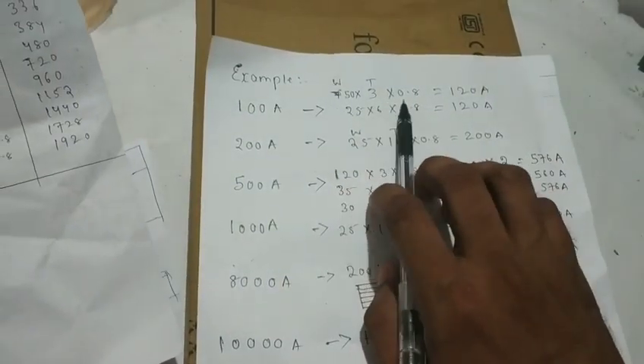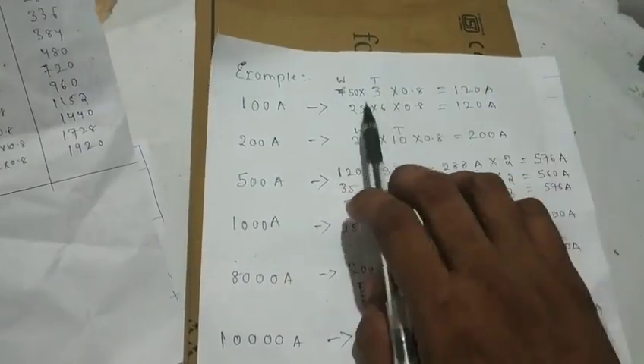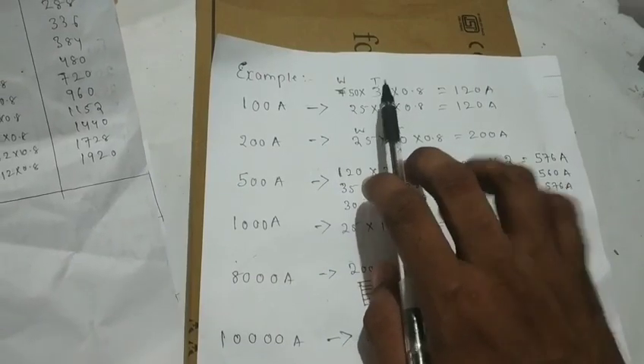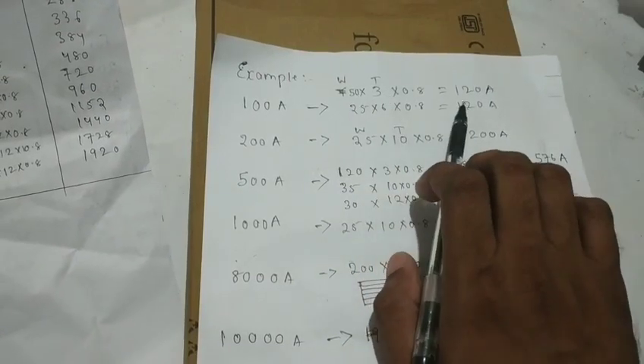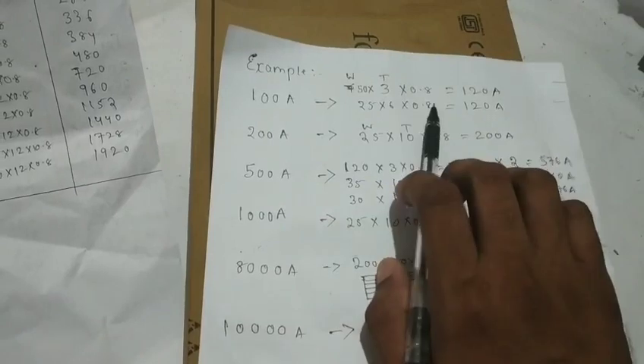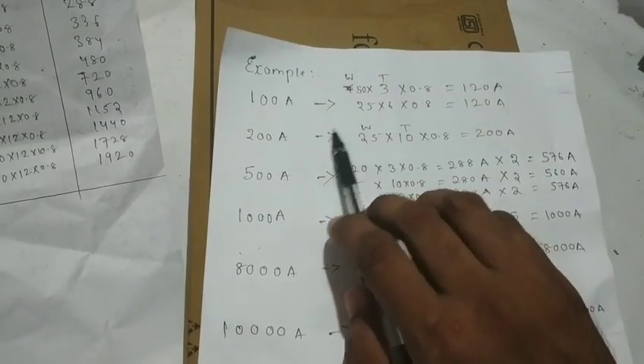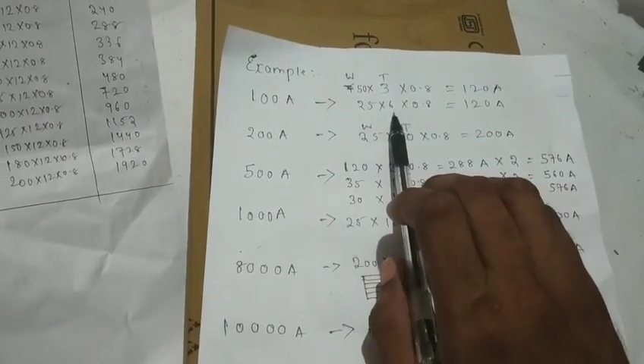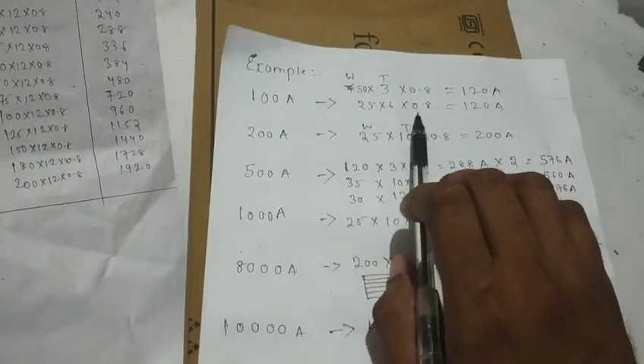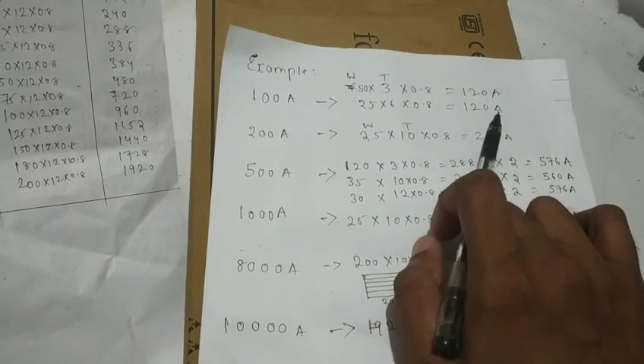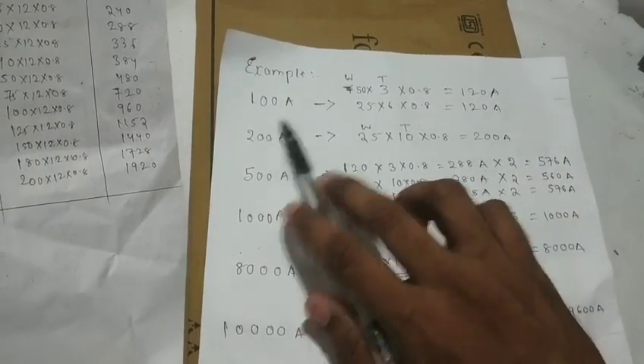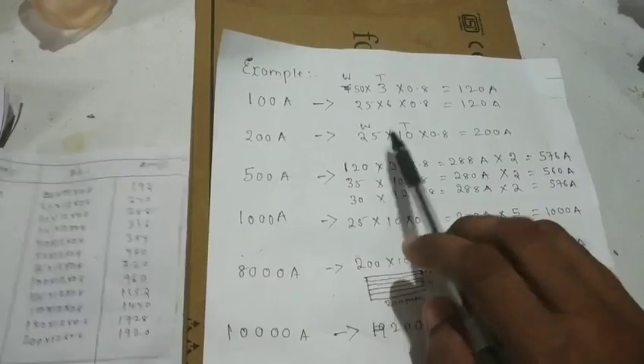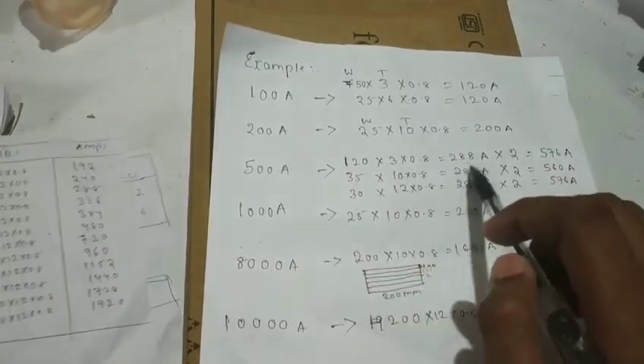50mm width and 3mm thickness: 50 × 3 × 0.8 = 120 amps. That gives us coverage for 100 amps. Also, 25mm width and 6mm thickness: 25 × 6 × 0.8 = 120 amps. Both combinations give 120 amps, which is sufficient for 100 amps.